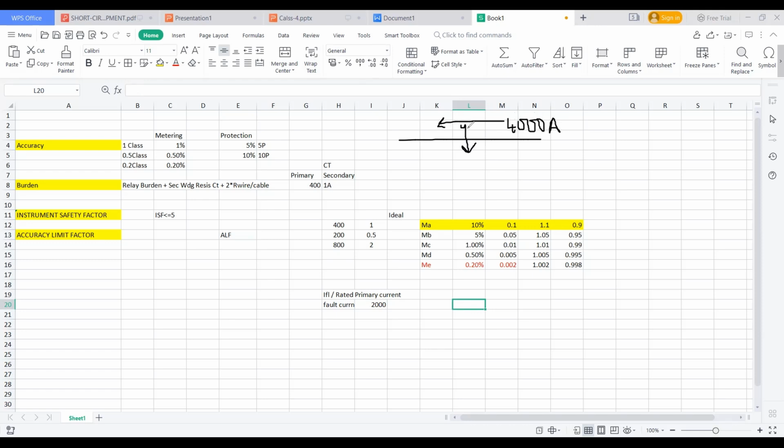This is the fault recording we use for grading all the relays. So up to 4000 amps, the CT should not enter into saturation. So what is the ALF then? 4000 divided by the primary current of the CT. The rated current of the CT is 400 amps. So 10 is the ALF here. ALF should be 10 in our case.